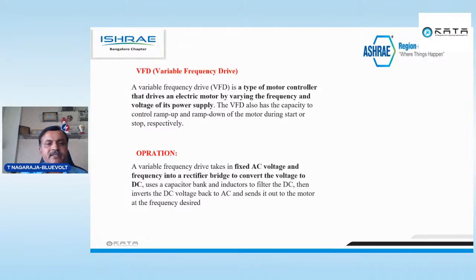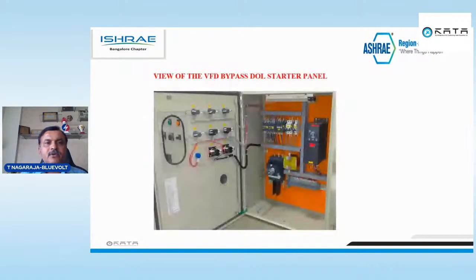A variable frequency drive takes a fixed AC voltage and frequency into a rectifier bridge to convert the voltage to DC. It uses a capacitor bank and inductors to filter the DC. Then it inverts the same DC voltage back to AC and sends it to the motor at a desired frequency level. So this is the view of the VFD bypass DOL starters.